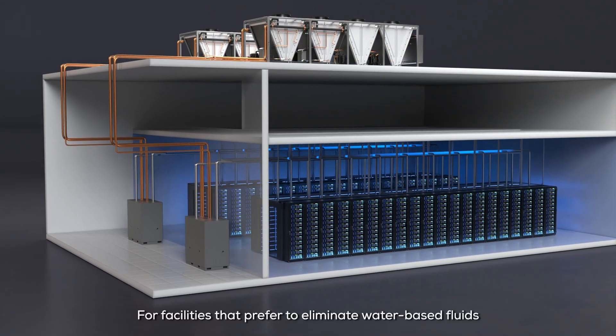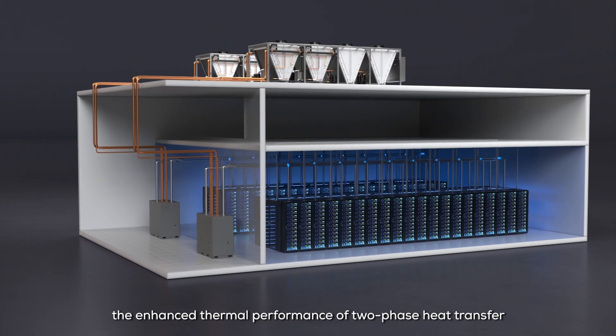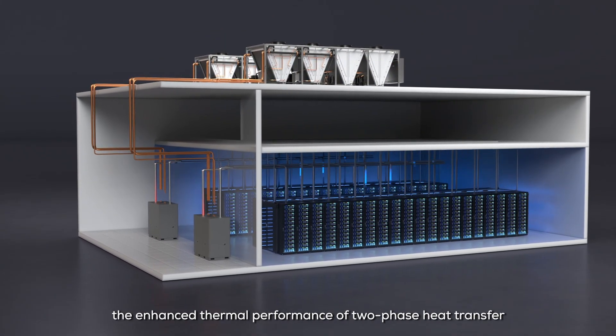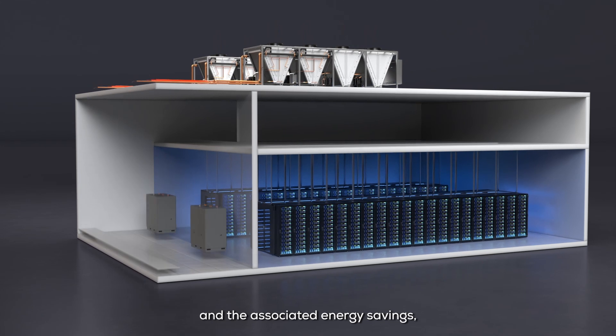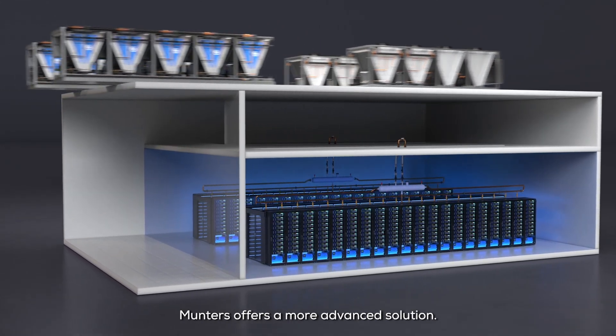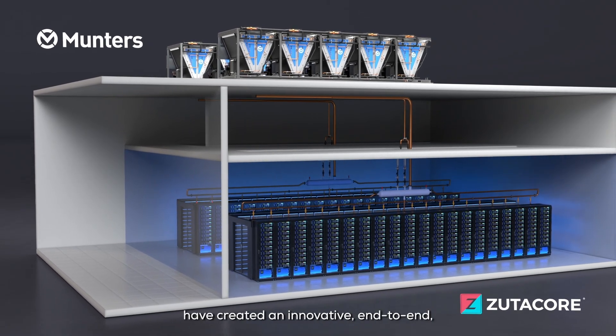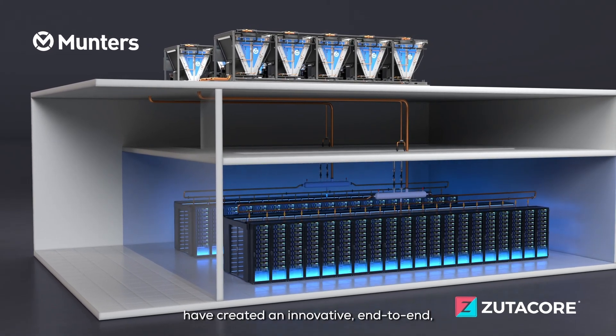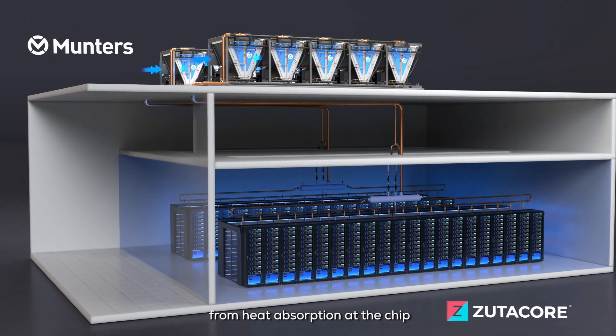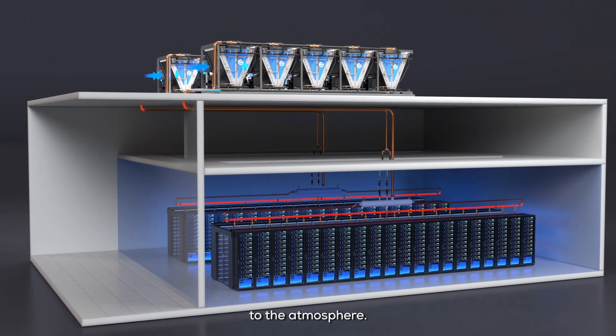For facilities that prefer to eliminate water-based fluids from their data halls, while also benefiting from the enhanced thermal performance of two-phase heat transfer and the associated energy savings, Munters offers a more advanced solution. Through a collaborative effort, Munters and ZutaCore have created an innovative, end-to-end, two-phase liquid cooling solution from heat absorption at the chip all the way to heat rejection to the atmosphere.